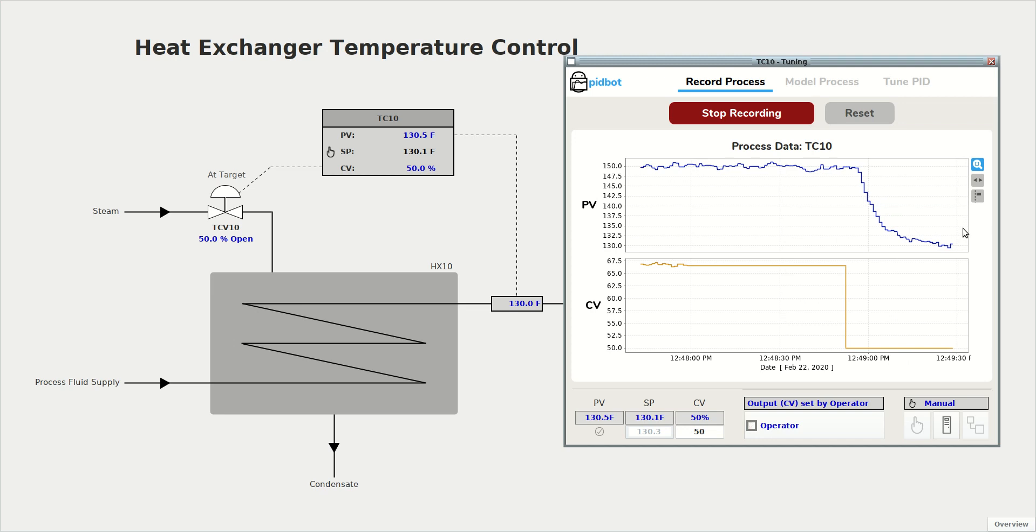And it's also a good idea to bump the process again and in the other direction in case it behaves a little bit differently on the way up. I'll go to 85% on the valve.